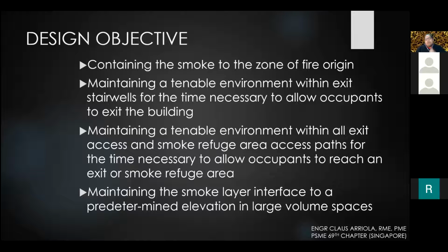So here are the design objectives: containing the smoke to the zone of fire origin - you see the keyword, containing. Maintaining a tenable environment within exit stairwells for the time necessary to allow occupants to exit the building. Maintaining a tenable environment within all exit access and smoke refuge area access paths for the time necessary to allow occupants to reach the exit or smoke refuge area. Lastly, maintaining the smoke layer interface at a predetermined elevation in large volume spaces.